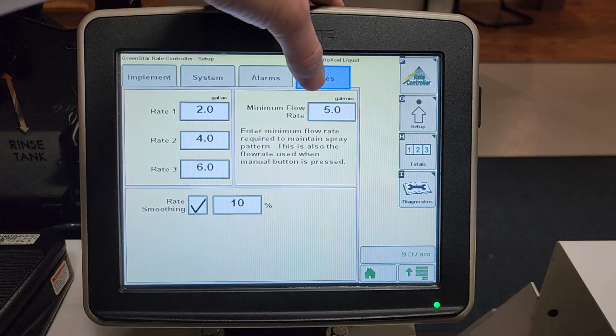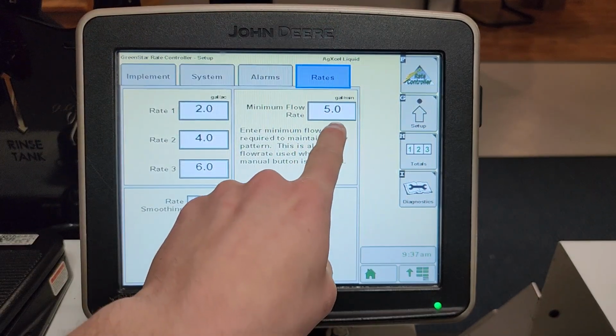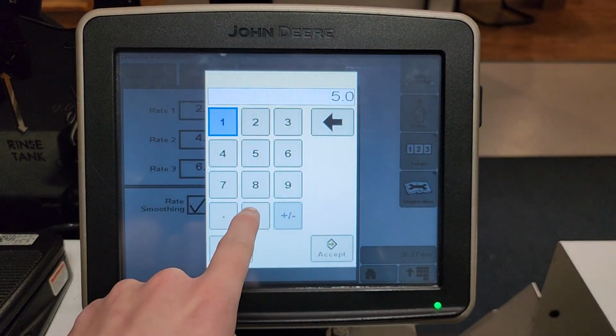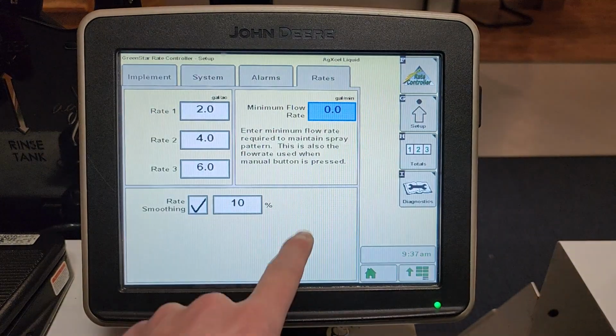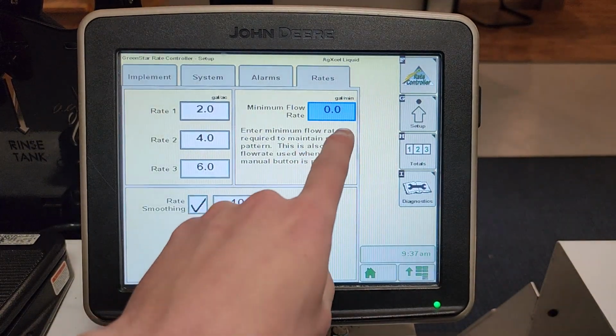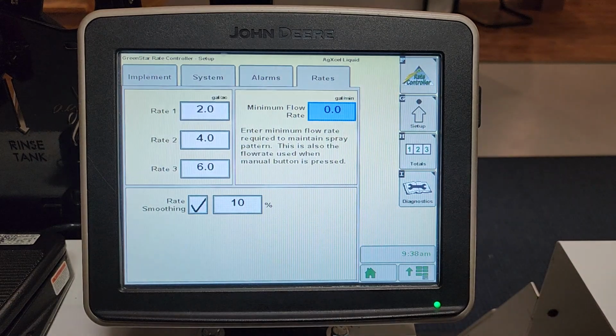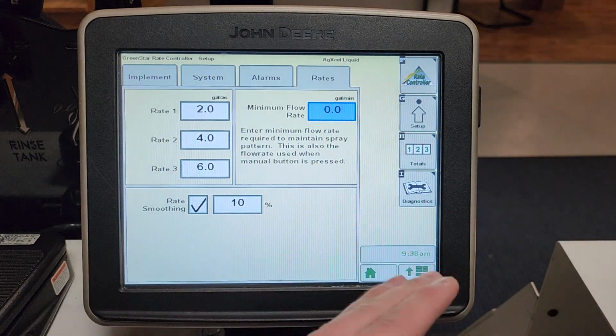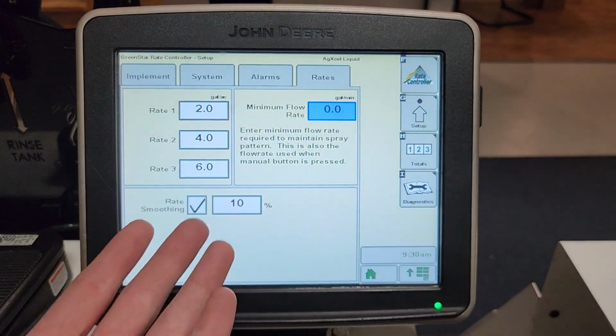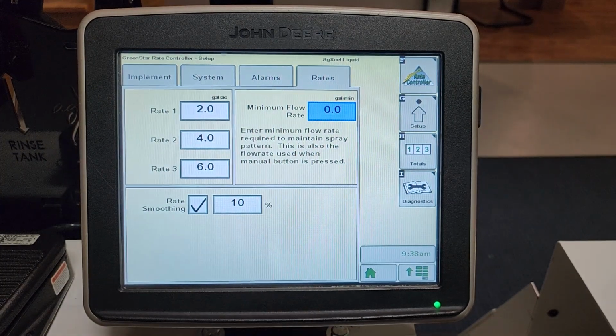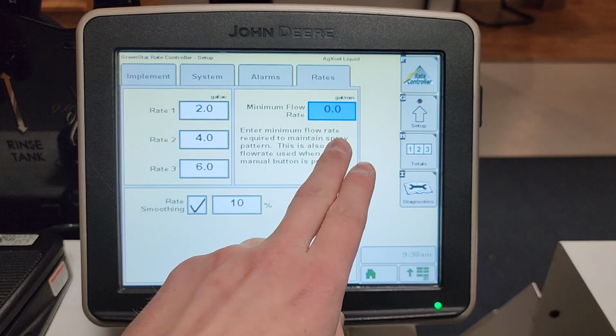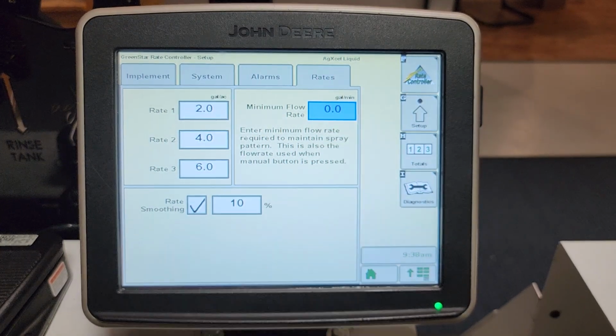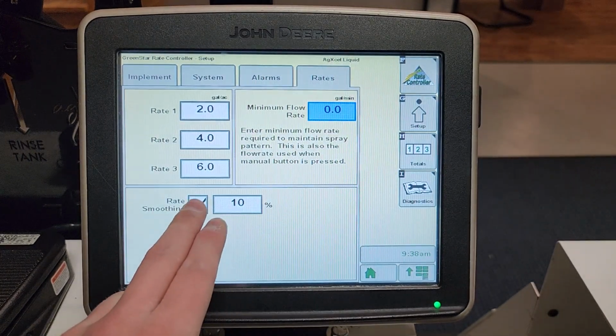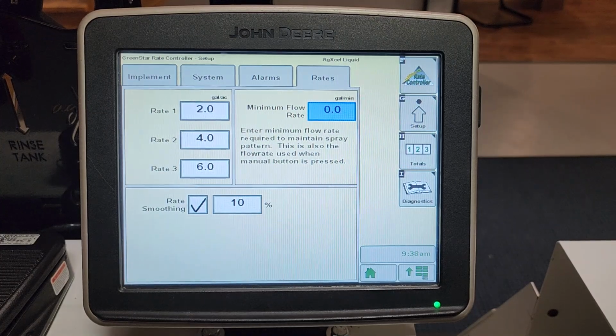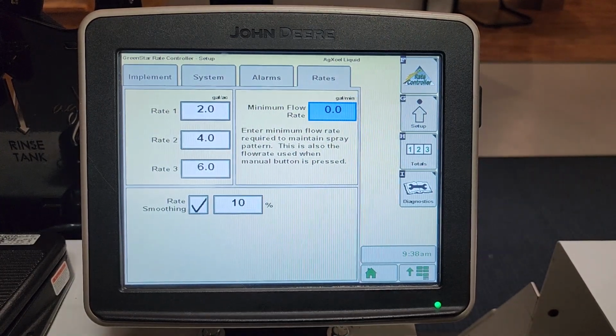Your minimum flow rate, you'll always want to have this set to 0. If you have it set to a different number, like in my case, I have it at 5, what will happen is even if I never do go below 5 gallon per minute, sometimes my pump still won't even go below, say, 6 gallon per minute, say if I wanted to run a rate of 5.5 gallon per minute. So you'll always want to have your minimum flow rate set at 0 because that can cause flow issues. And then your rate smoothing you'll have checked and at 10%. And that is the whole setup on the Greenstar.